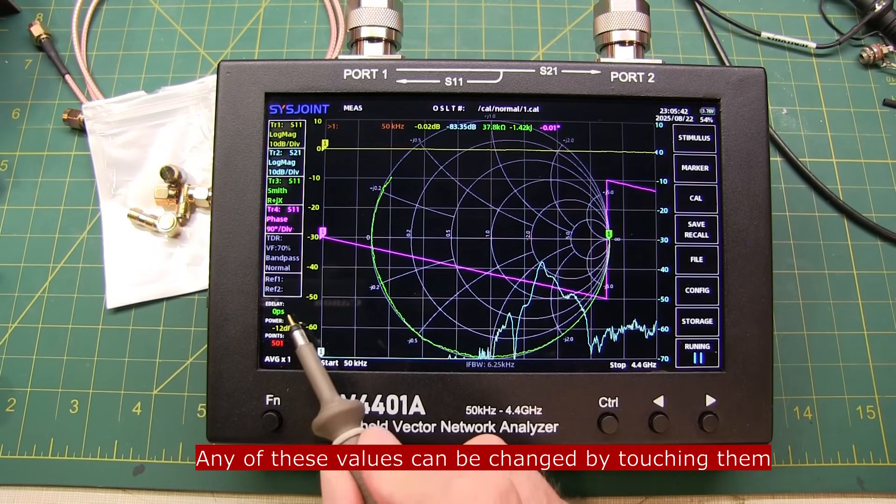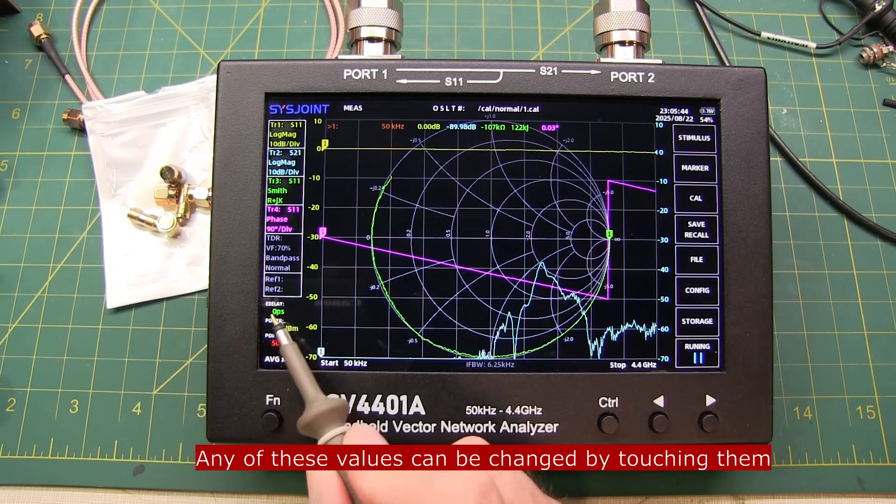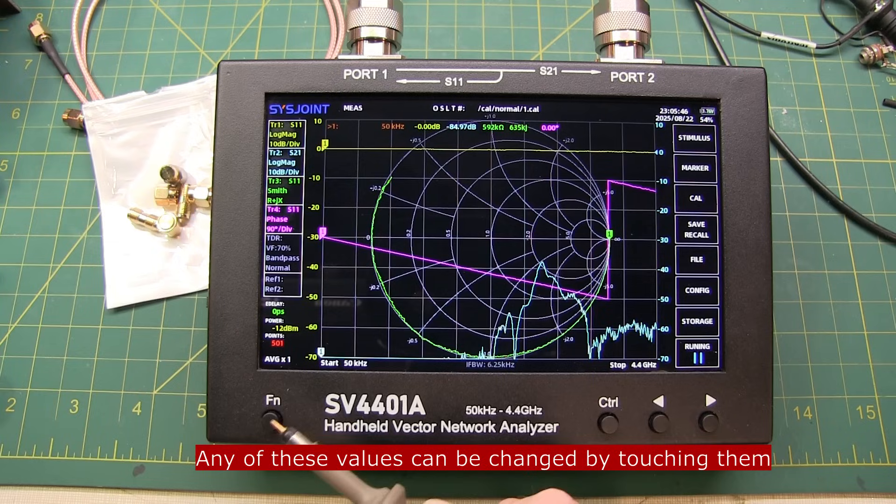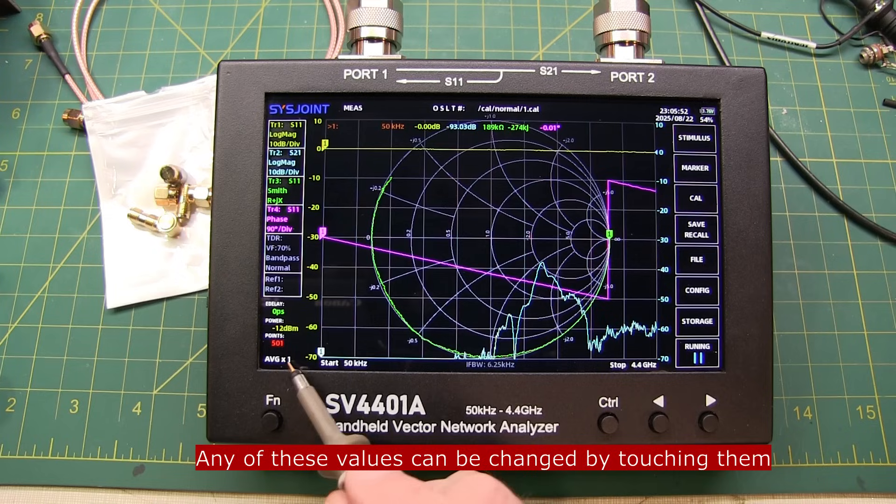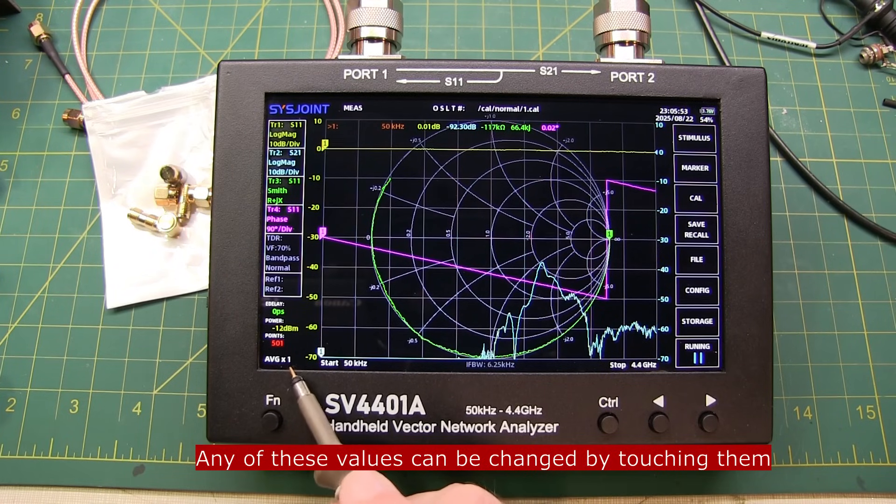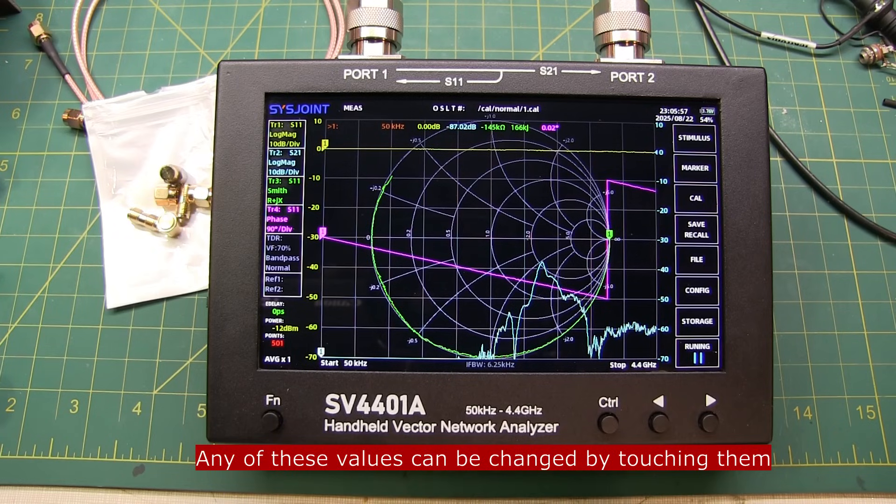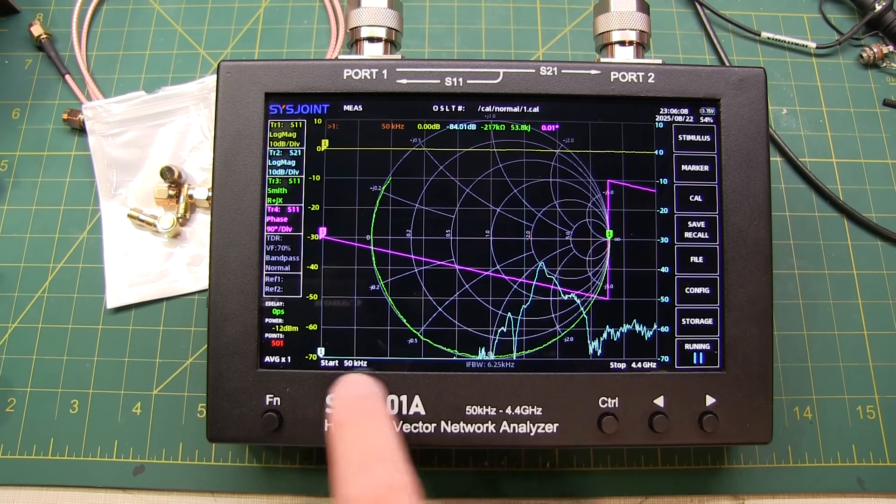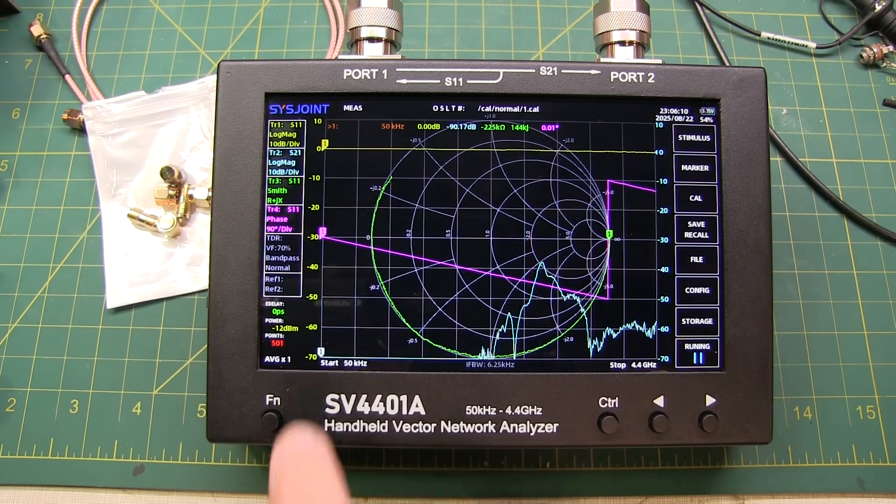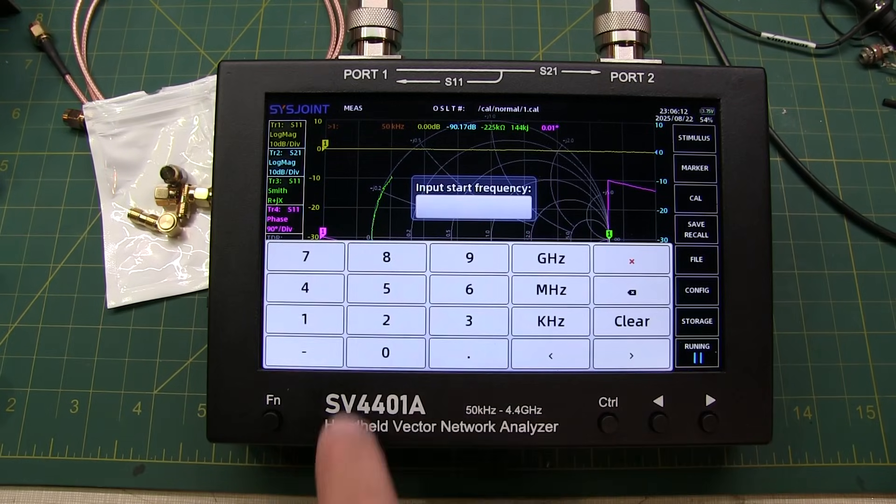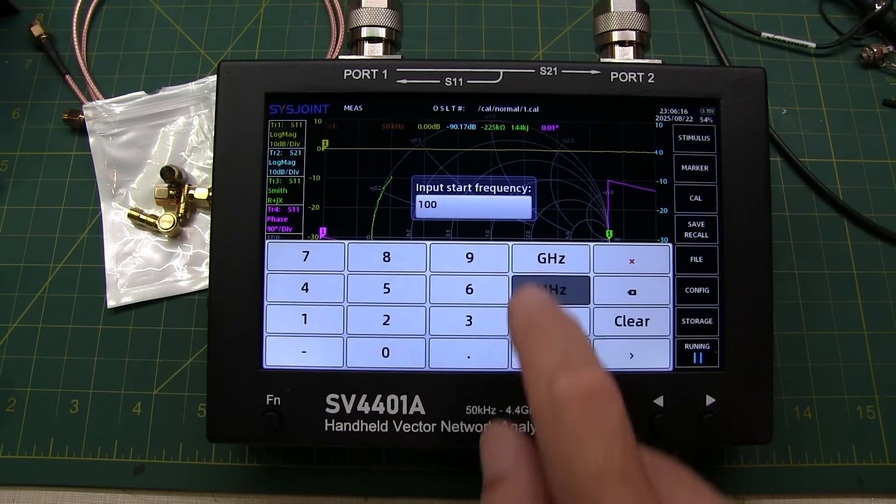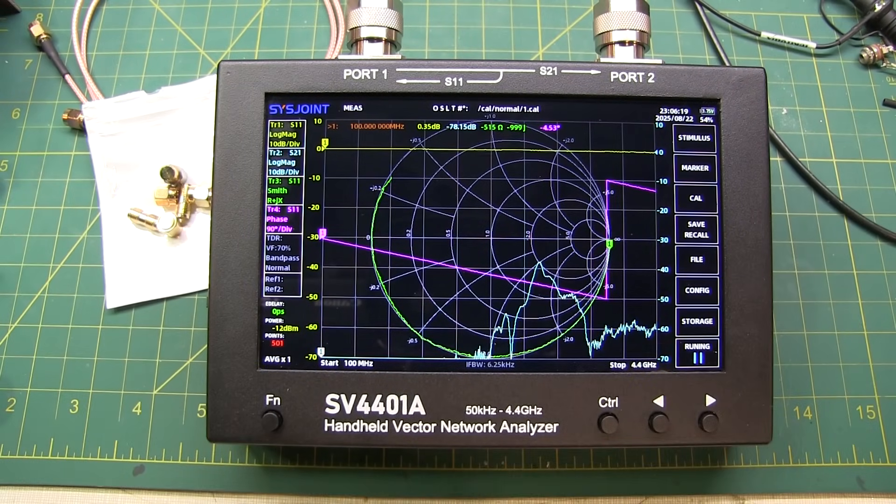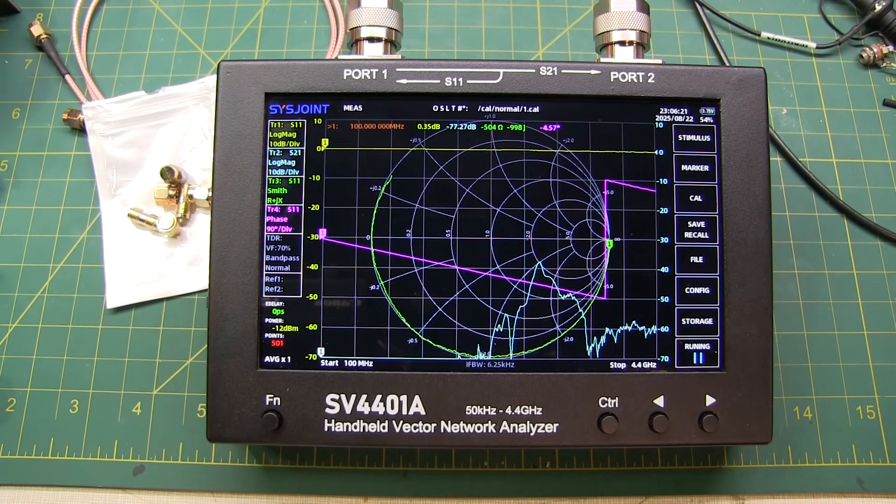The screen area also will show you the electrical delay for port extension applications. It will show you the output power and the number of points right on the screen. It will show you if you're doing any averaging. And then the frequency, the start and stop frequency shown here. You can shortcut going in and changing these parameters by simply touching on them. And now I can actually put in a new start frequency if I want to. So I'll put in say 100 megahertz. I can dial that in. And now I'm starting at 100 meg. I didn't have to bring up a menu to go do that.